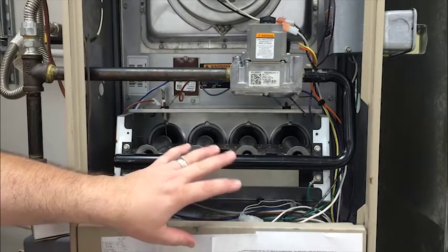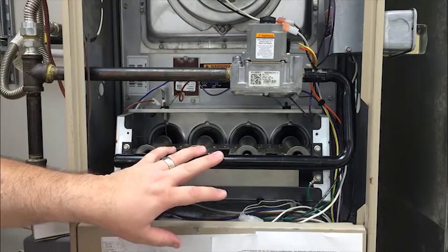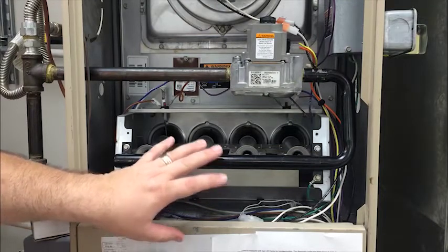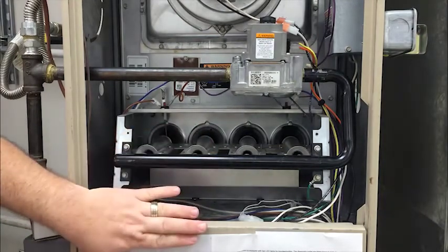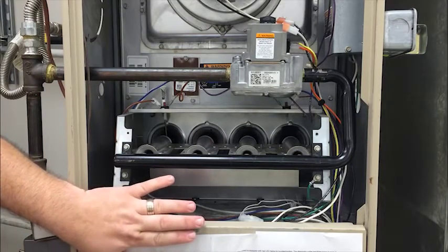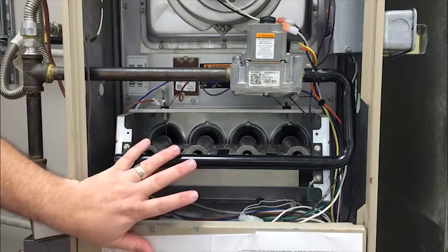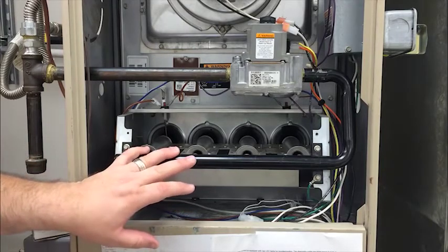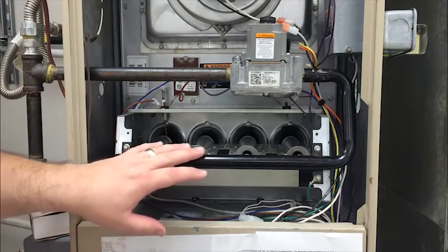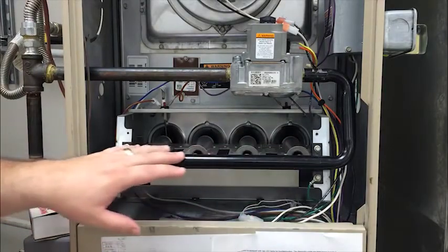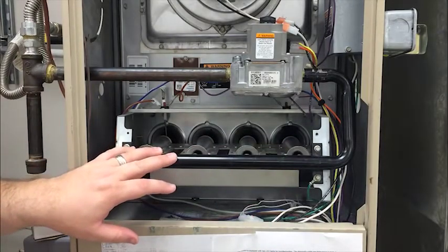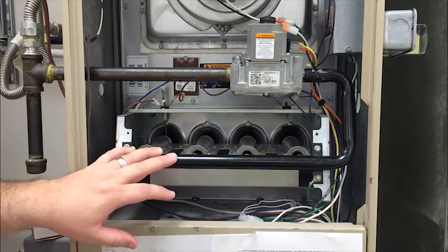What that means is we turn the furnace's fan on but leave the heating system off. That'll engage the blower motor right below the burners, and that'll start pushing positively pressurized air across the heat exchanger. If any of the heat exchanger cells are breached or cracked, the air from the blower will enter one of these cells, and we can simply do a standing match test to see if the flame is blown around, extinguished, or distorted in any way.